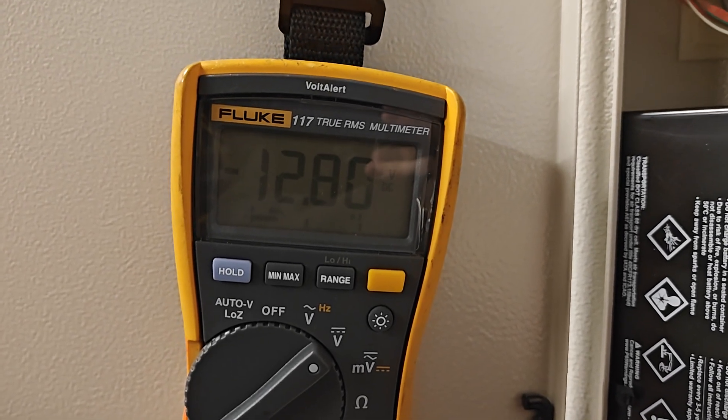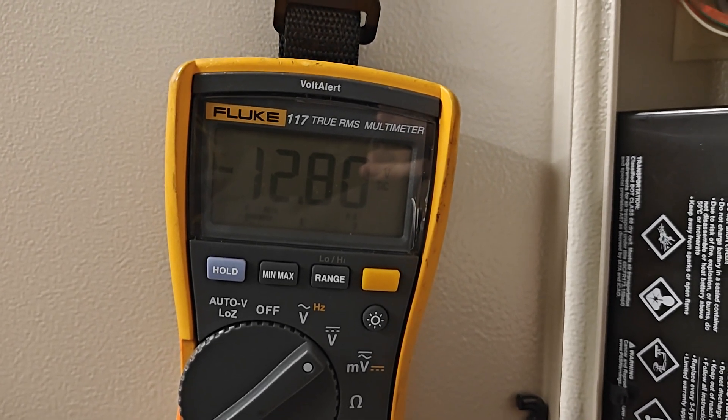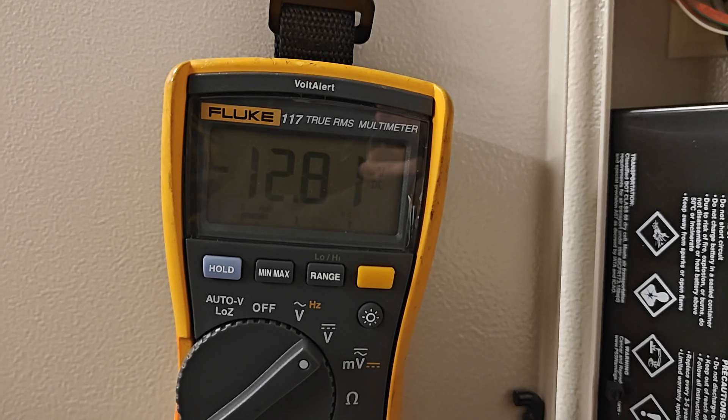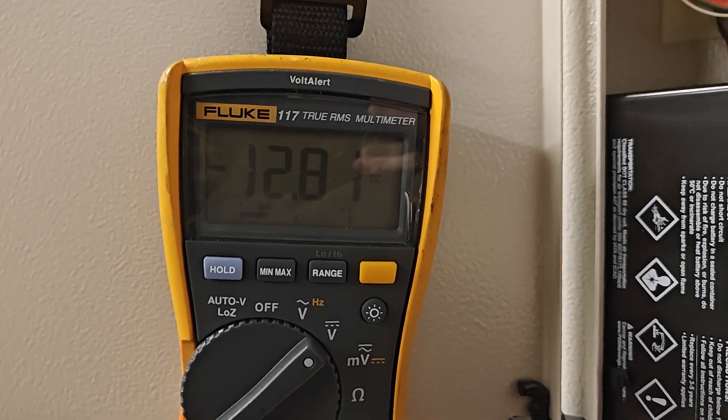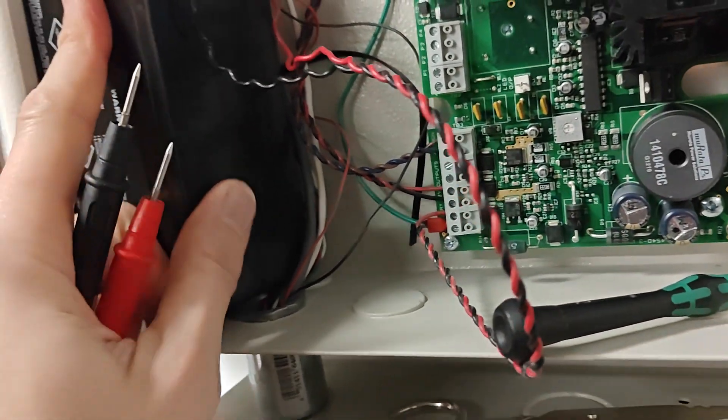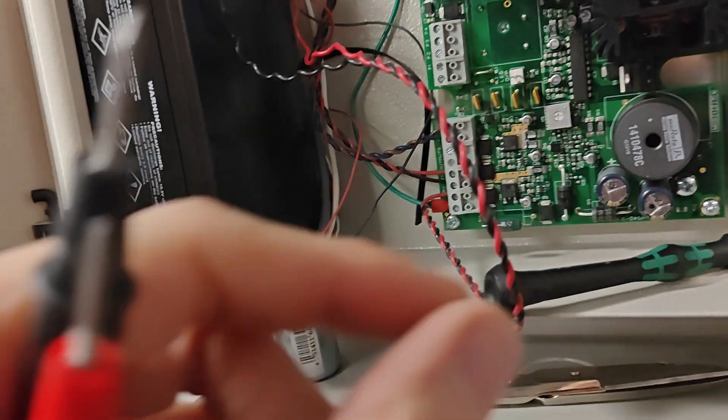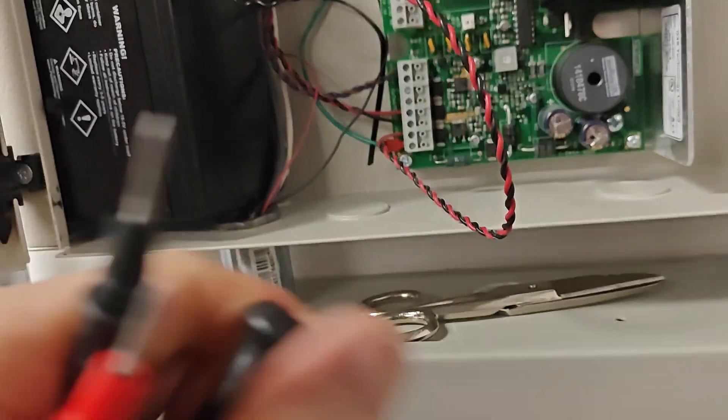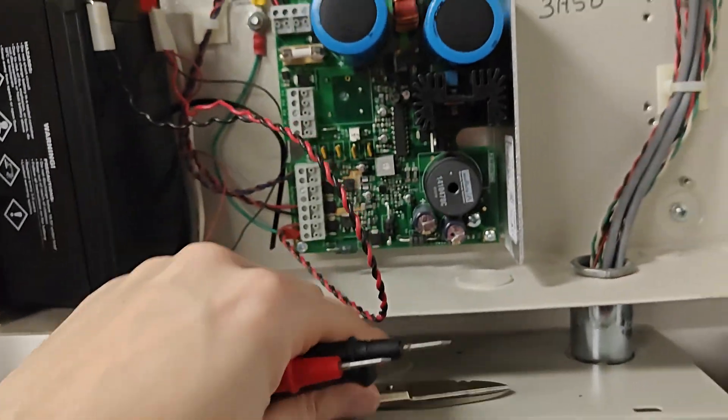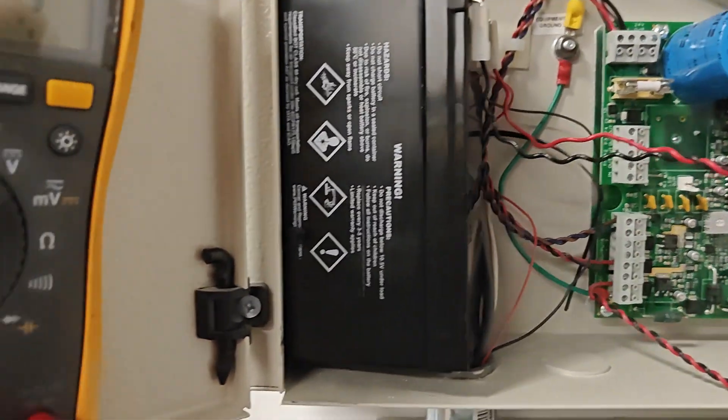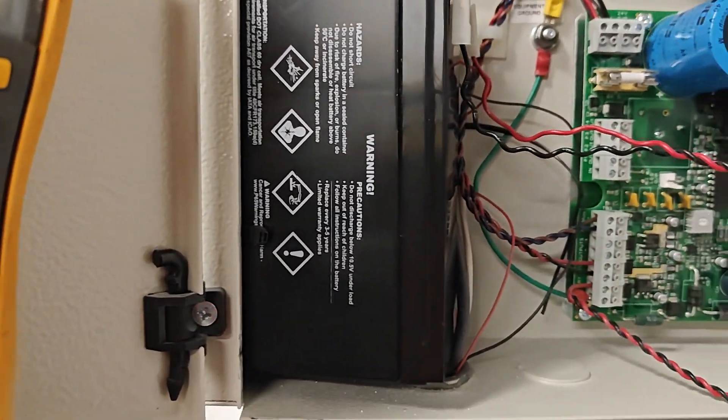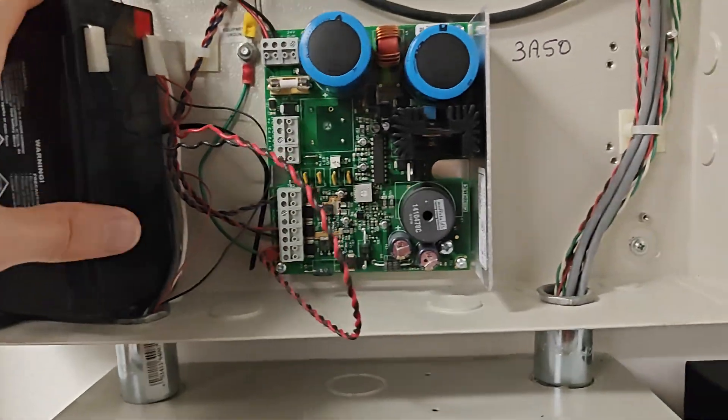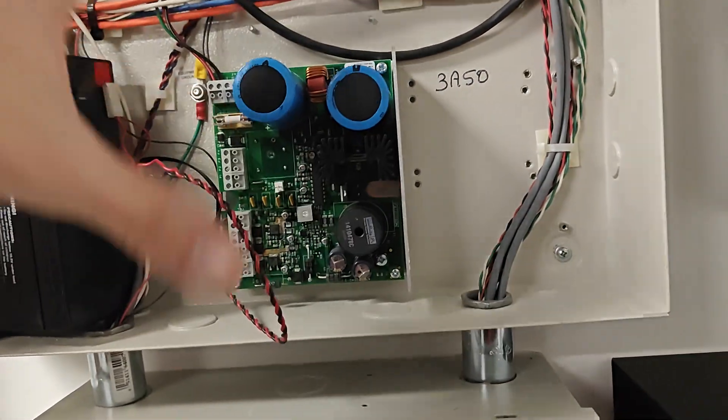There it is, there's 81. So basically it's charging the battery up a little higher than 12 volts, which is fine. But that kind of troubleshooting or maintenance can definitely save your batteries, save your power supply, and save your entire device.